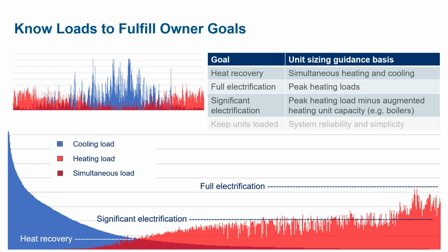Many projects, especially in cold climates, are successful since peak heating days can be infrequent, resulting in significant electrification. Additionally, in systems with centrifugal heating chillers, it may be necessary to keep a unit loaded to avoid entering the surge region. This results in a unit capacity similar to that for the heat recovery goal.